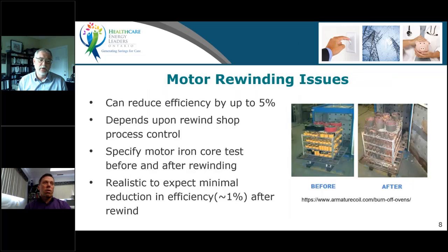And if somebody, go ahead, Michelle. Yeah, I was going to say, somebody had a throttling valve, they decided to just open it on their motors, and they see that their motors start burning out. That could be a reason, because by removing pressure drop, you may actually end up overloading your motor. We'll look at that in a second. I've got a slide that looks at that.